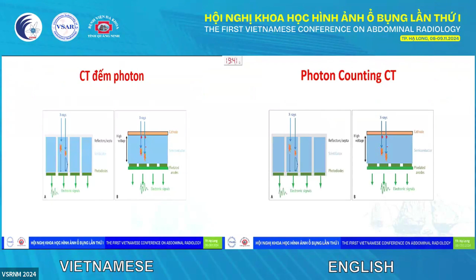The advantage of a PCCT, or photon counting CT, is that there are differences within the physics of how the image is generated. Routine CT studies use a scintillator to generate visible light when the incident X-ray photon hits them, and the light is recorded by a photodiode. However, photon counting CT scans use a semiconductor to generate positive and negative charges, with the negative charges going to anodes in the detector, which generate electronic signals.